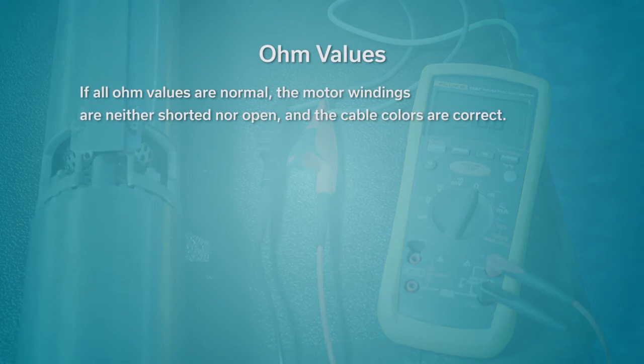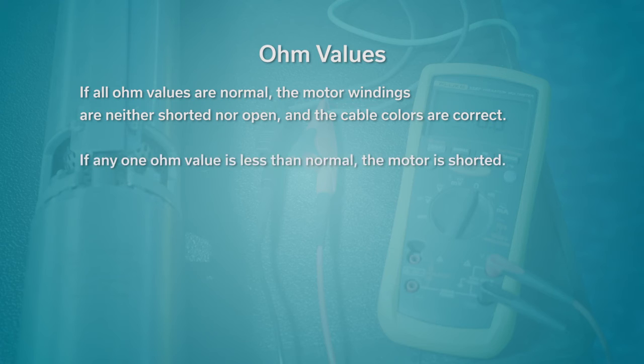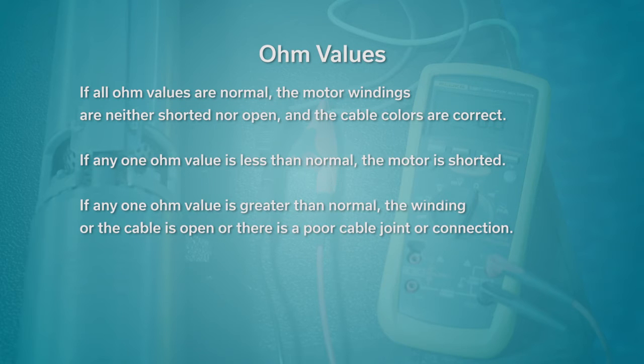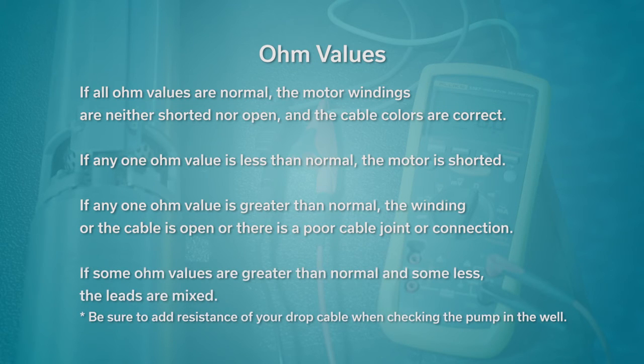If all ohm values are normal, the motor windings are neither shorted nor open, and the cable colors are correct. If any one ohm value is less than normal, the motor is shorted. If any one ohm value is greater than normal, the winding or the cable is open, or there is a poor cable joint or connection. If some ohm values are greater than normal and some less, the leads are mixed.